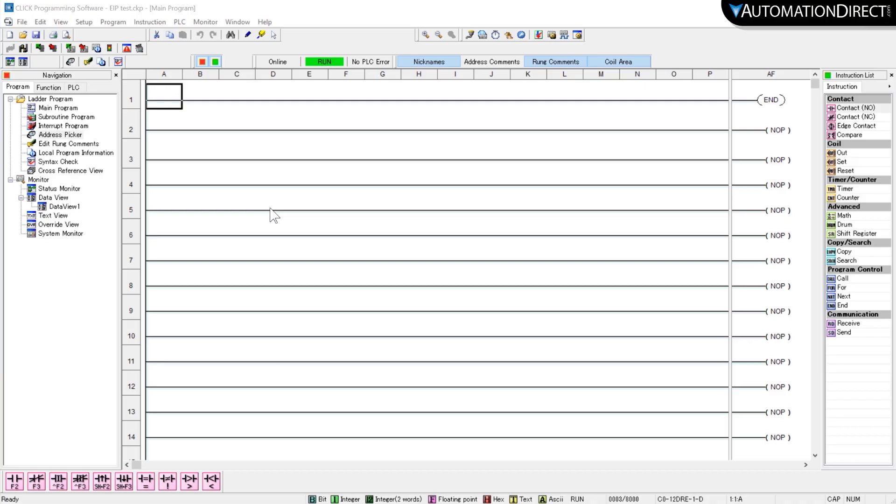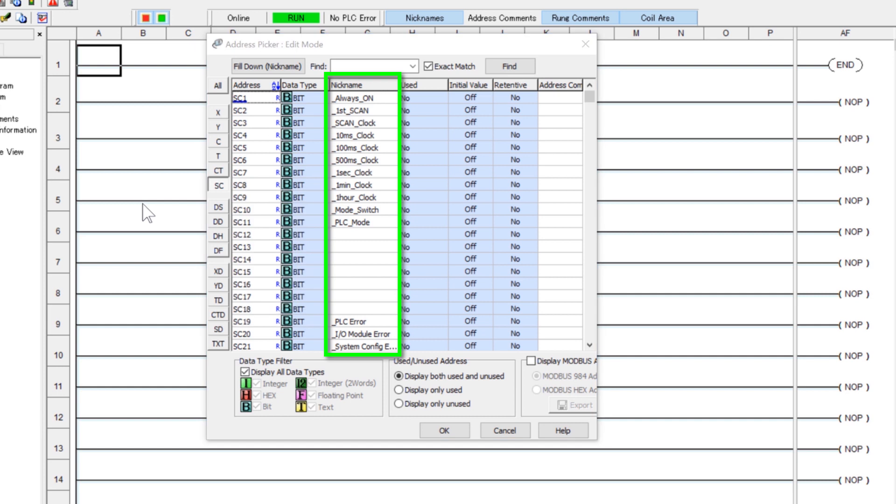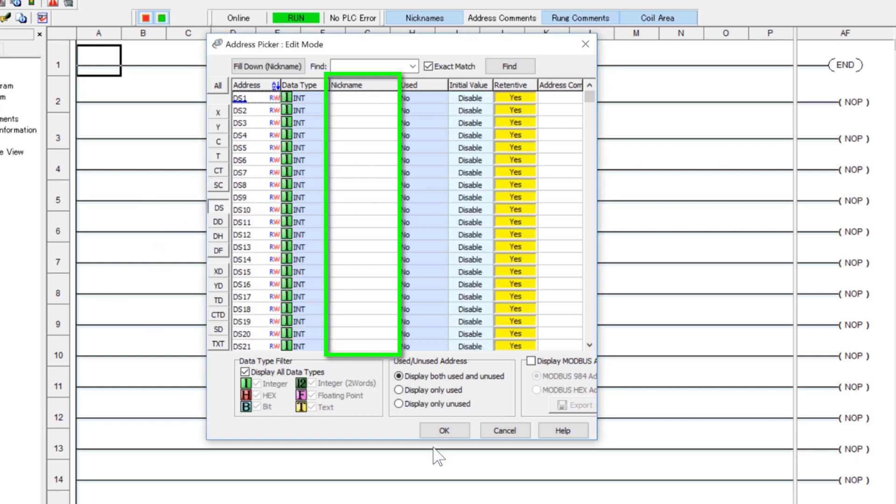Now there is a caveat to this tag import. Only the addressing that has nicknames placed here will be exported in this process. So if you want these addresses to export to your HMI, you will need to place nicknames for them here.